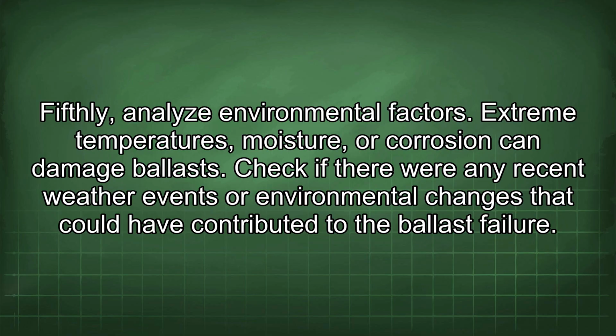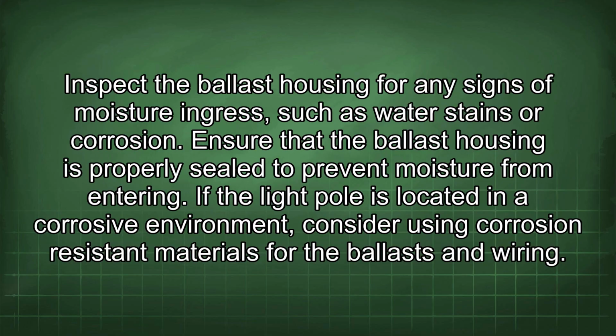Extreme temperatures, moisture, or corrosion can damage ballasts. Check if there were any recent weather events or environmental changes that could have contributed to the ballast failure. Inspect the ballast housing for any signs of moisture ingress, such as water stains or corrosion. Ensure that the ballast housing is properly sealed to prevent moisture from entering. If the light pole is located in a corrosive environment, consider using corrosion-resistant materials for the ballasts and wiring.